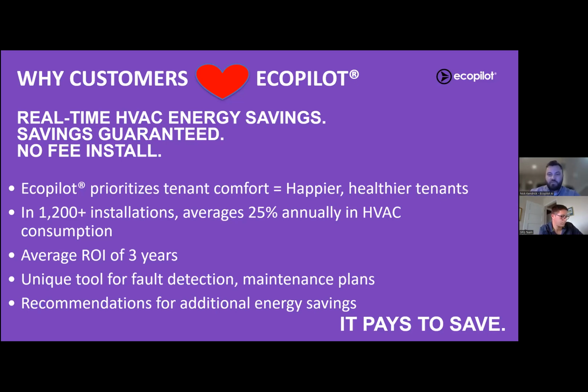Say you sign up with Ecopilot, after the first month you'd end up with a report that we'd put together. We'd figure out how to optimize a little bit further, make some small tweaks, often with this extra layer of monitoring on your building. We find some other opportunities. It's kind of a light energy audit in a way, nothing as sophisticated as what SPG does or anything, but this adds another lens to the building, and we're able to come up with some more additional recommendations. Maybe it's adding a VFD to a pump, or maybe there's a need for a 3-way valve, things like that. So that's another benefit.